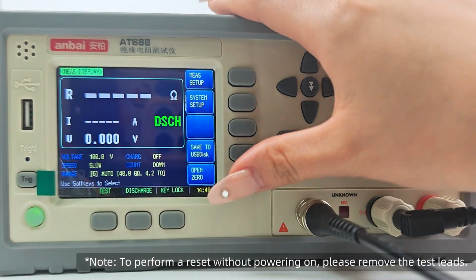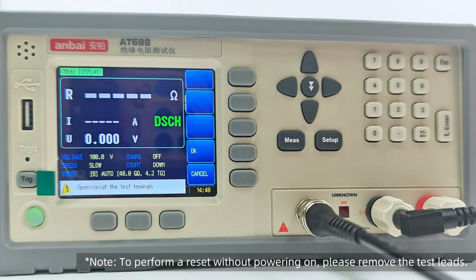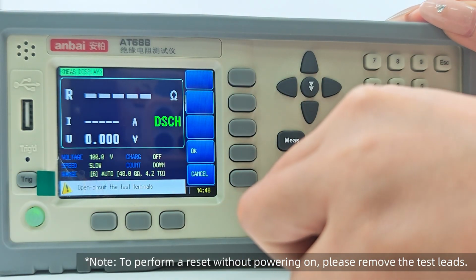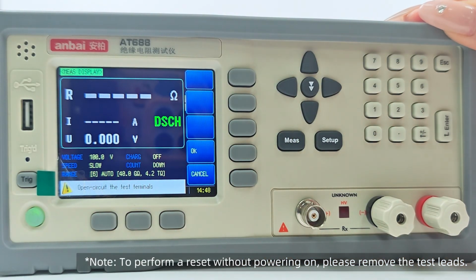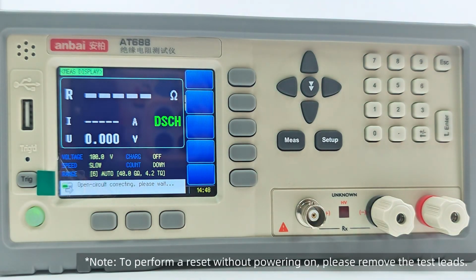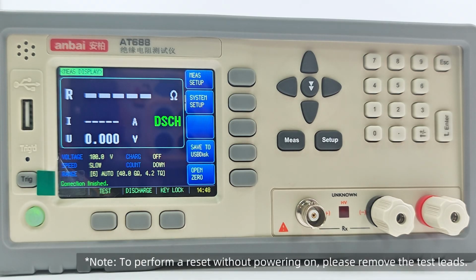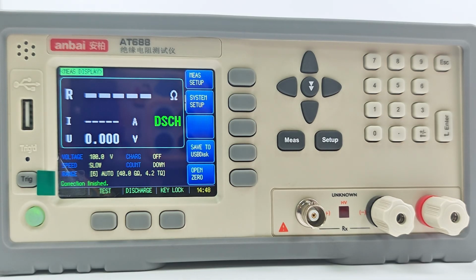Perform an open circuit zeroing operation on the instrument. To achieve high precision measurements, zeroing calibration is necessary. Press the button to clear the zero value. When the prompt text appears, remove the test cable, then press the button to confirm. Once the progress bar is completed, the zero value clearing is done.